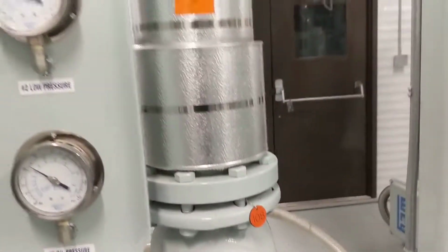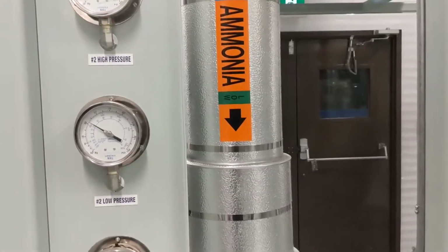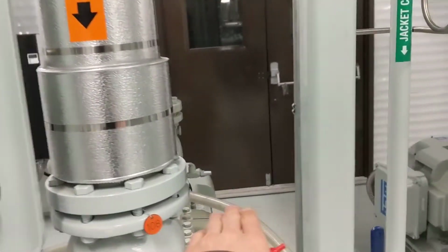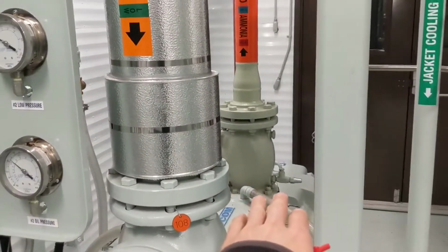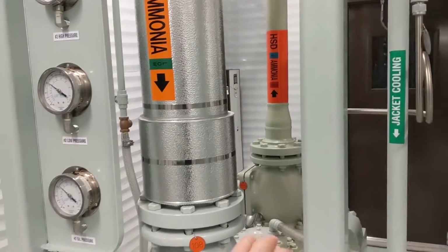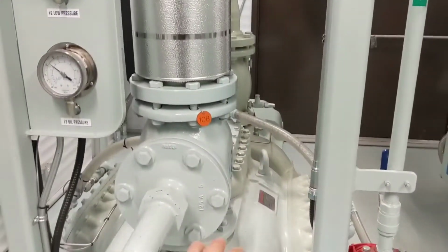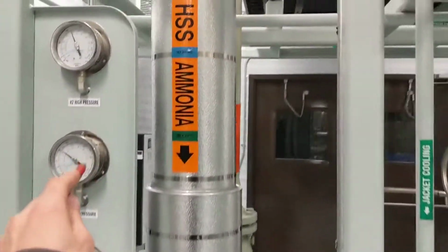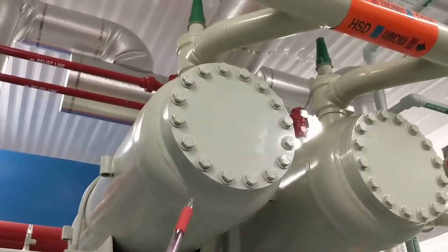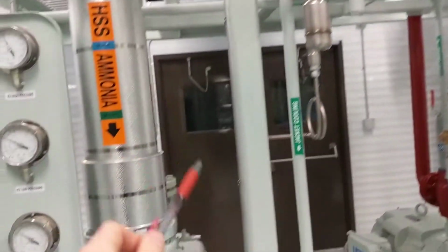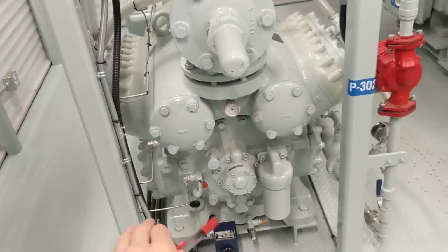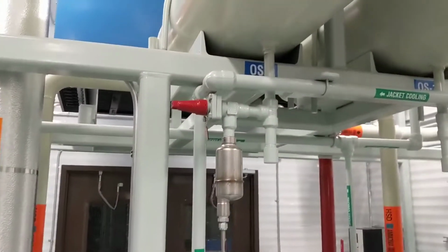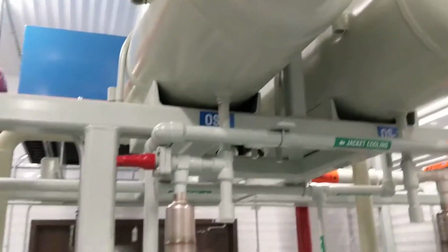What Ultimate Fabrication has done is they've designed this to maintain constant suction pressure, so the compressors are going to ramp up and ramp down. So the VFDs will change the speed the motor turns at, which changes your suction pressure or your low pressure, and by managing the low pressure they get really good oil separation, which means unlike our old plant, we're no longer going to be adding oil to the compressors all the time and draining it out of the chiller all the time like we used to.